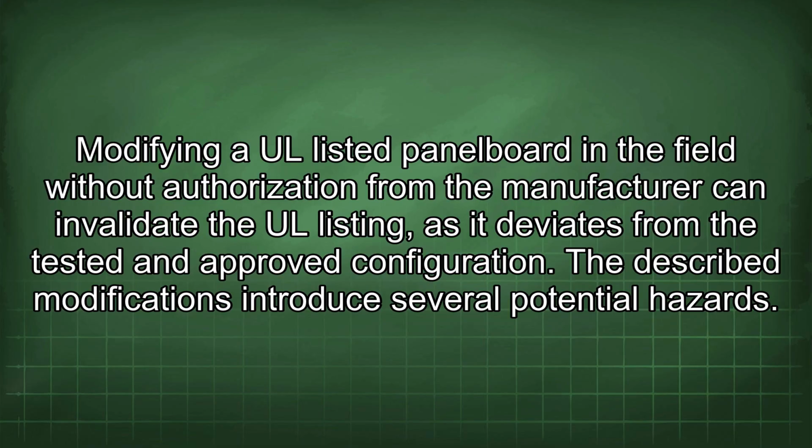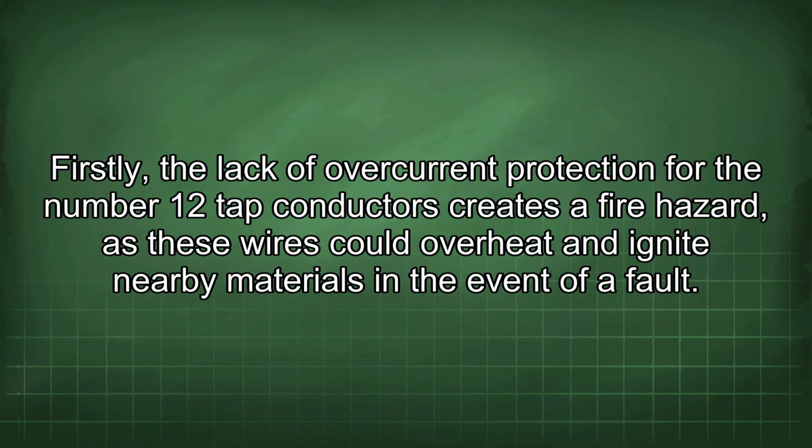The described modifications introduce several potential hazards. Firstly, the lack of overcurrent protection for the number 12 tap conductors creates a fire hazard, as these wires could overheat and ignite nearby materials in the event of a fault.